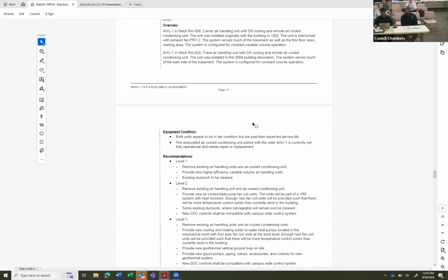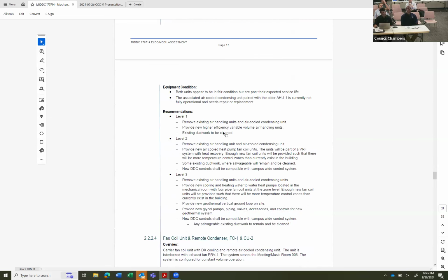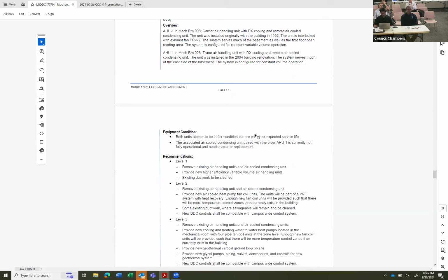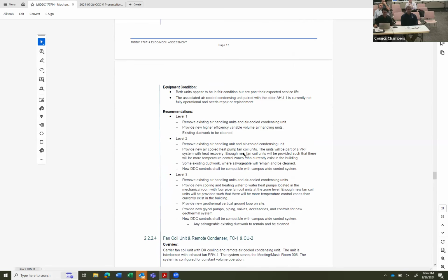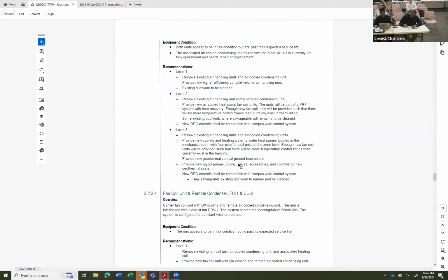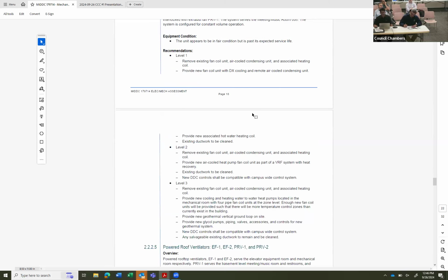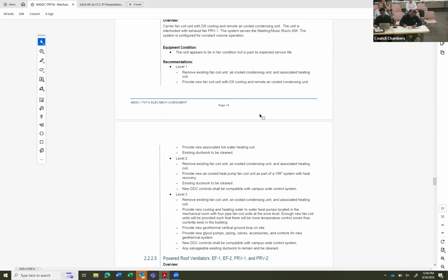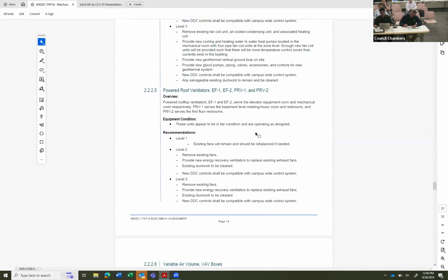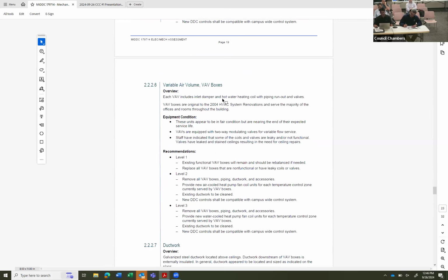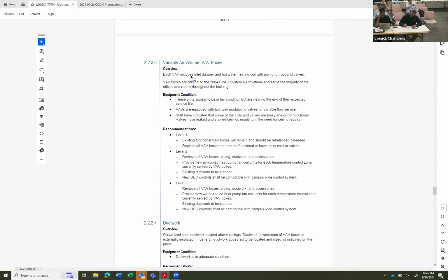And again, similar to the city hall options, the level 1 option for the air handling units that serve the building would be to remove them and replace with newer variable volume, higher efficiency air handlers. Level 2 is removing the air handling units and replacing with smaller fan coil units that can be distributed to each zone, and same concept with level 3 in the geothermal system. And the fan coil system, I won't go through all the details, is similar to the air handlers and the variable air volume boxes, VAV boxes.